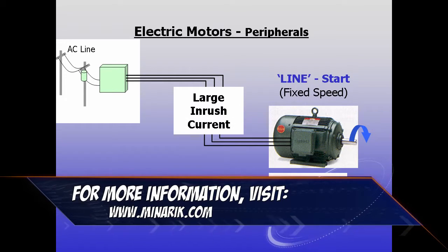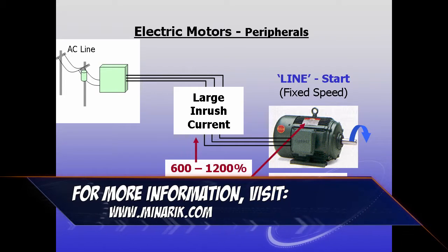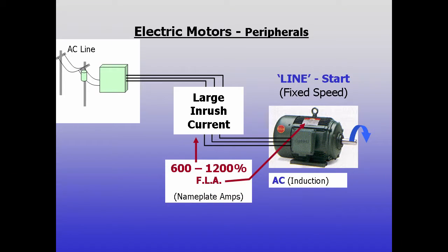When AC motors are started from the line, they draw large amounts of inrush current. Inrush can be as much as 6 to 12 times nameplate amperage depending on the load. This lasts for a few seconds until the motor gets to rated speed.